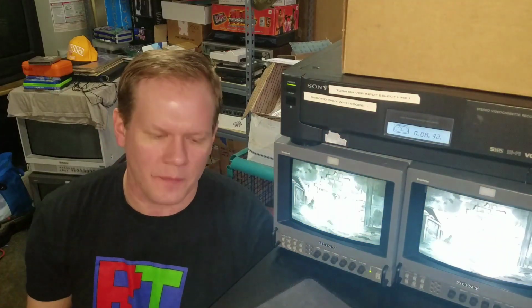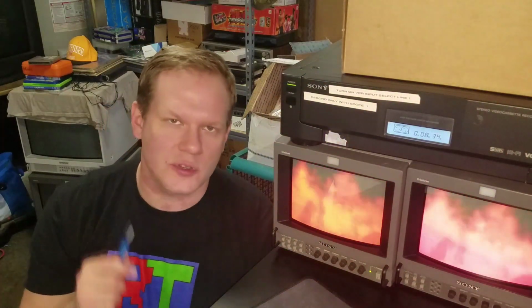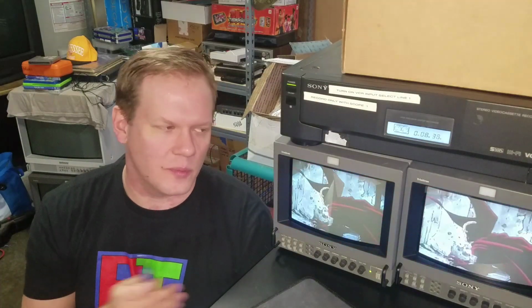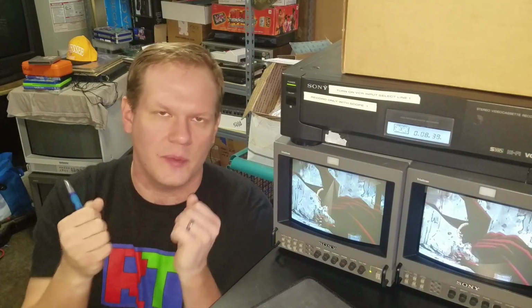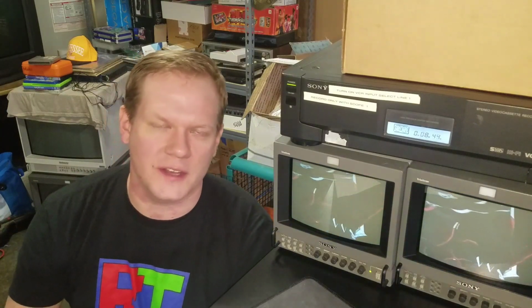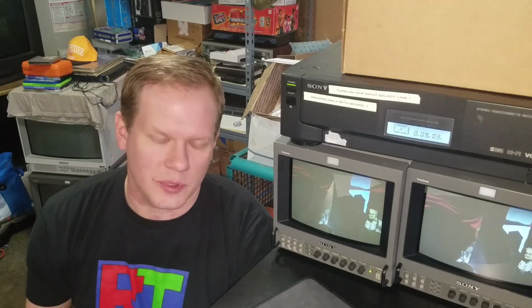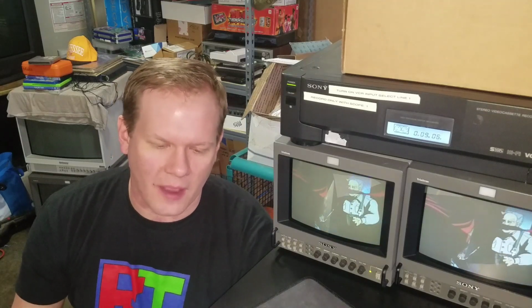That's something to remember, and those temperature changes, along with the physical movement of picking these up and moving them around, can affect your calibration. First off, temperature changes can affect your components internally and cause them to possibly fail and need changing, or just fall out of spec, especially in a climate like mine where you get freezing and thawing and then hot temperatures throughout the summer. We have a full 4-season climate here in Tennessee, and we get a lot of temperature change. So that's something to think about, how that can affect it.